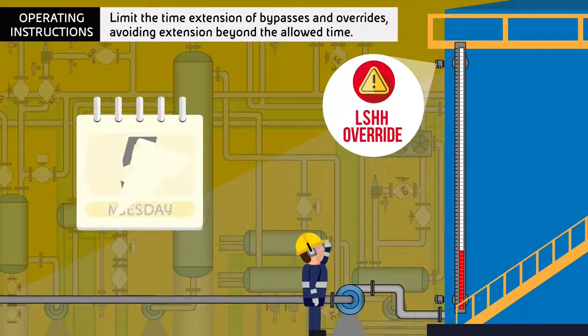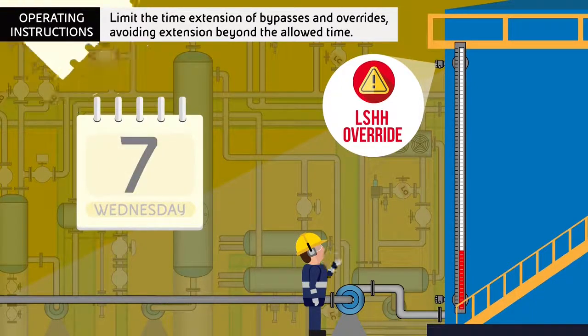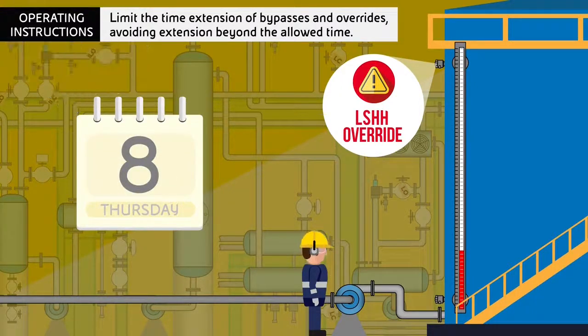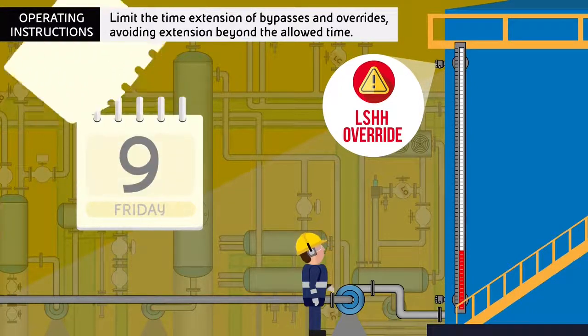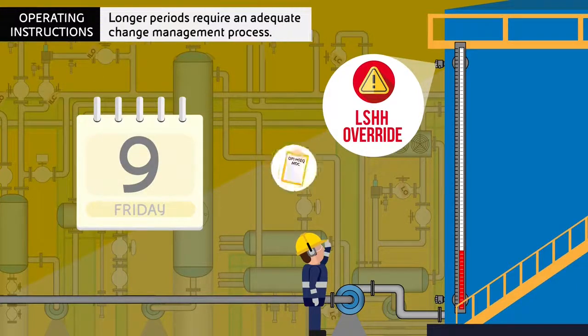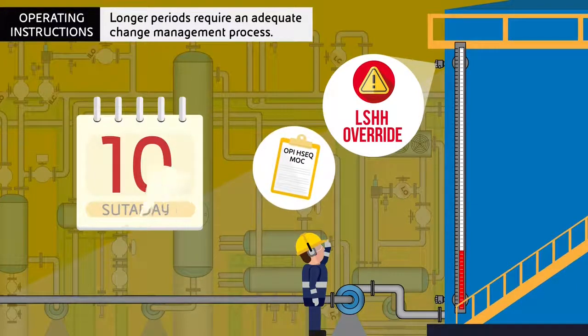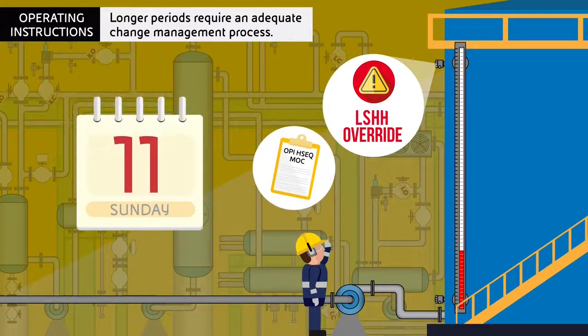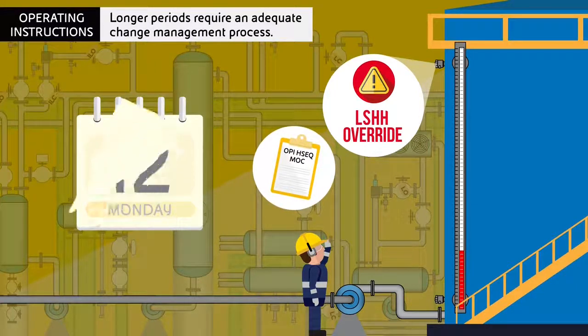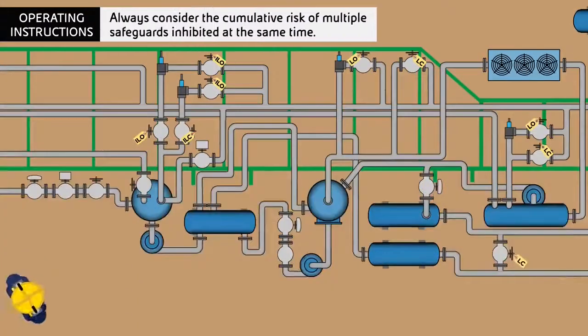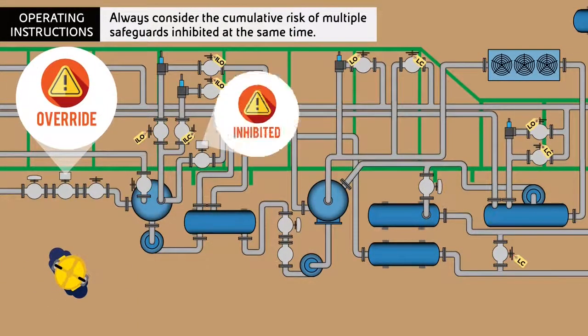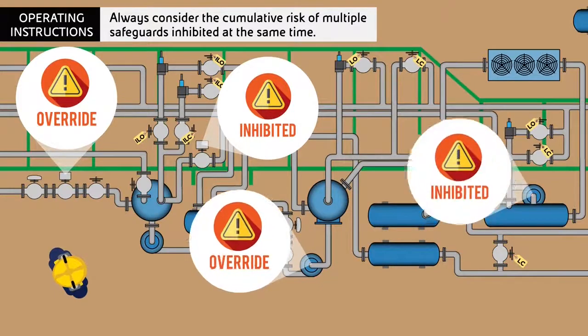Limit the time extension of bypasses and overrides, avoiding extensions beyond the allowed time. Longer periods require an adequate change management process. Always consider the cumulative risk of multiple safeguards inhibited at the same time.